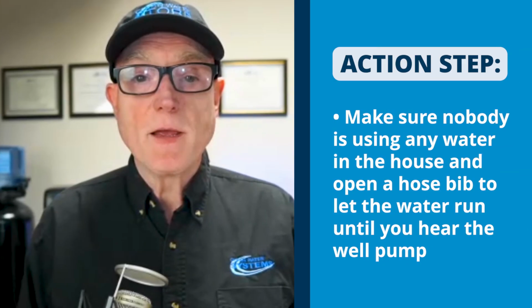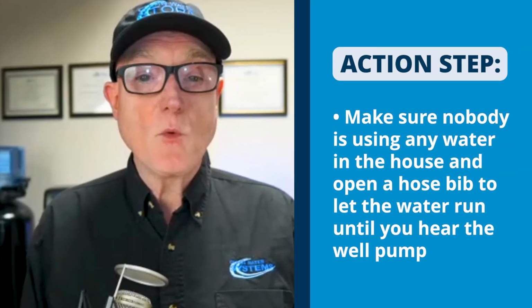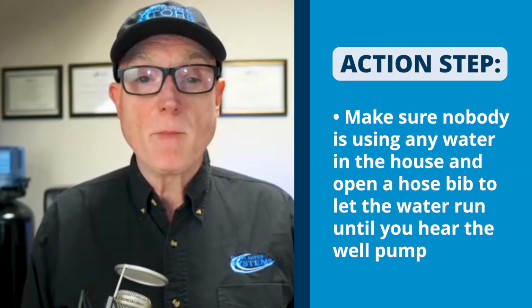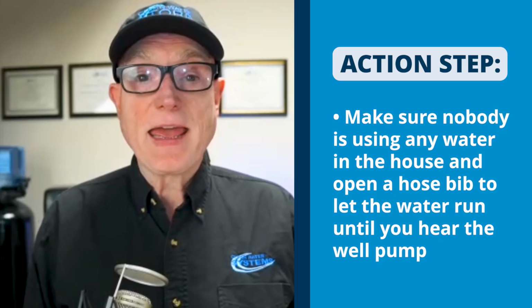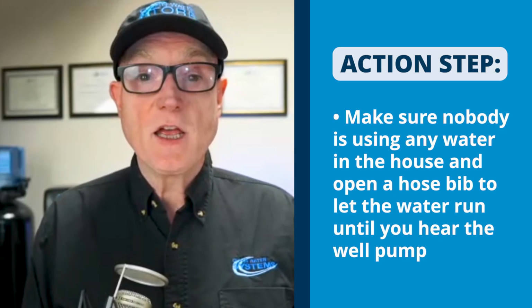So the first step is to make sure nobody's using any water in the house, and open up a spigot or hose bib and let the water run until you hear the well pump. When you first run the water, you're actually getting water out of the pressure tank, because the pressure tank is a captive air pressure tank and has a diaphragm or a bag in there that is under air pressure.